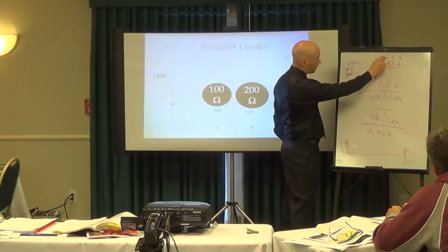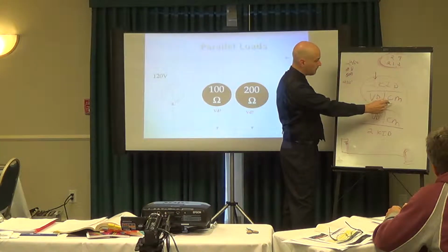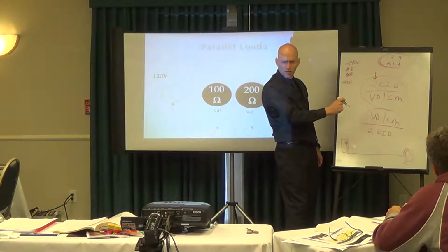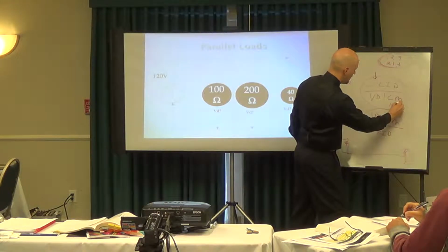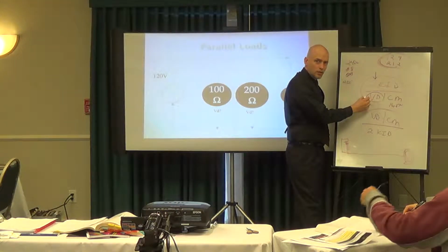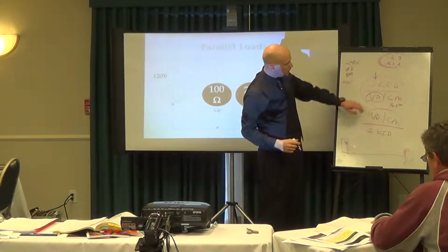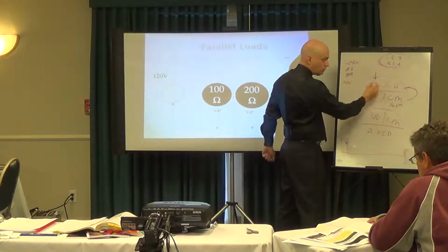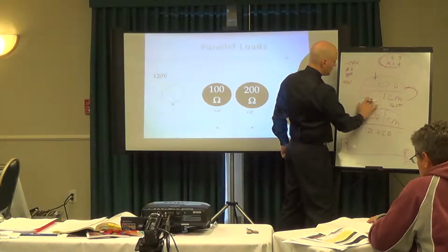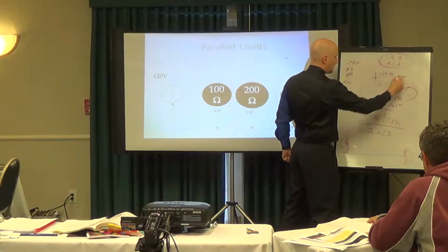At that point, we're just looking at 2 times 12.9 times 50 amps times 200 feet divided by 16,510. Remember I said we're always looking for a bottom number, right? So I'm just going to cover that up. I'm going to take this number here and divide it into the top numbers. Make sure I multiply these out first. So 2 times 12.9 times 50 times 200, and then divide that 16,510 into it, and bada bing.